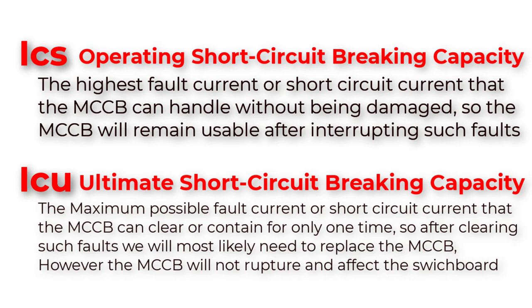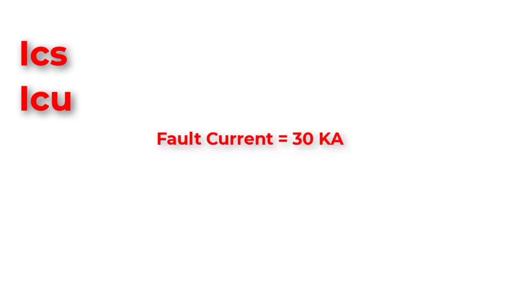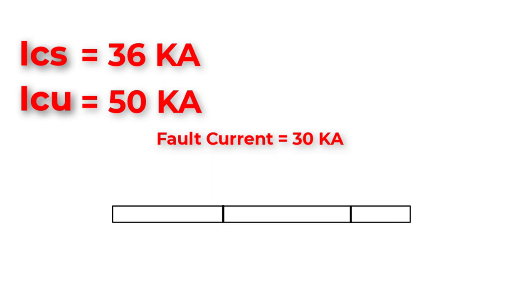We have to be extra careful during calculating and designing the short circuit analysis in the circuit. For example, assume that we have a fault current equal to 30 kilo-amperes, and our MCCB has ICS equal to 36 kilo-amperes and ICU equal to 50 kilo-amperes. At normal conditions, nothing will happen. If a huge fault causes the circuit to draw a fault current equal to 30 kilo-amperes — which is below ICS — the breaker will trip the fault instantaneously without any damage, and we will use this MCCB in the future without any replacements.